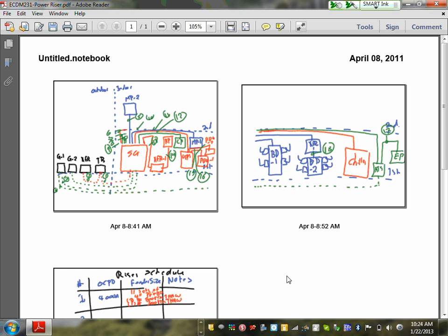Like the one you've mounted against the wall. It's our standard: if it's 2,500 amps or less, it's 24. When you get to 3,000, it's 36. 4,000 is 48. And then I think when you get to 5,000 amp, it gets to 54, 60.